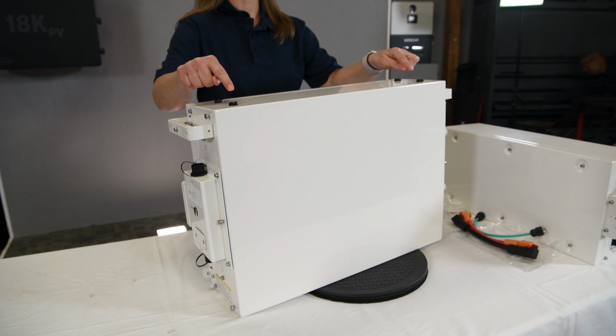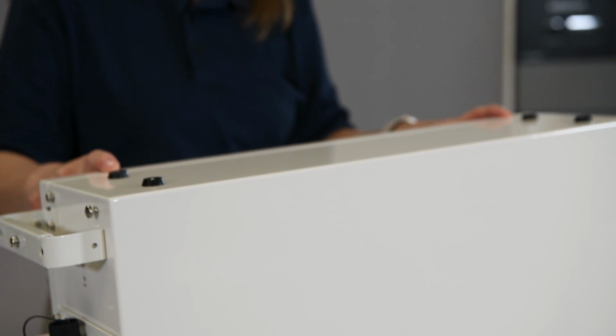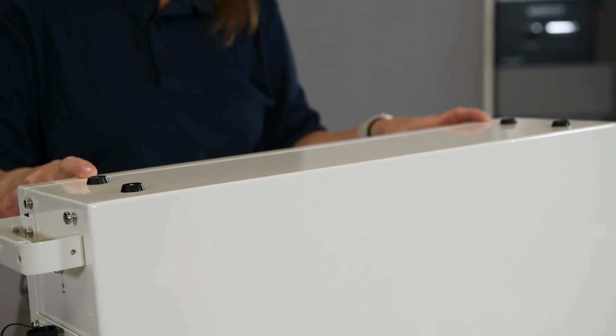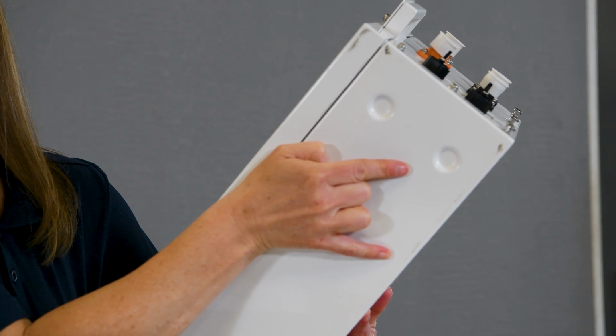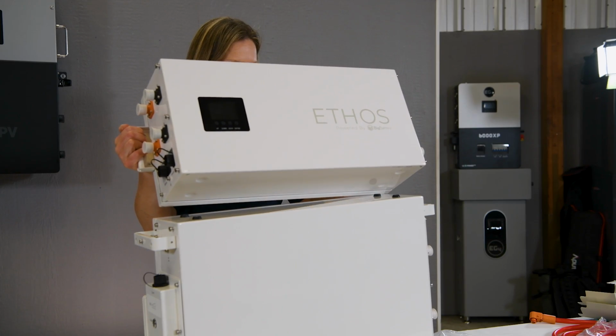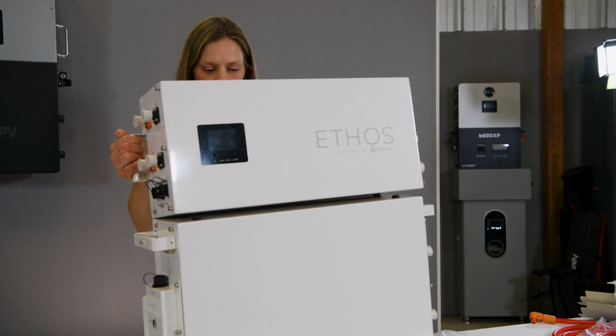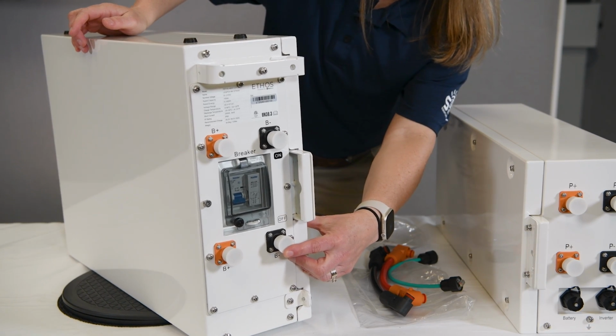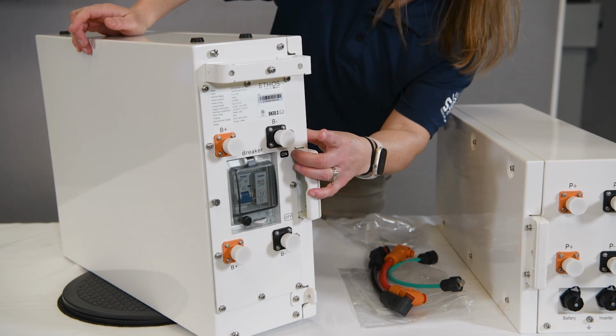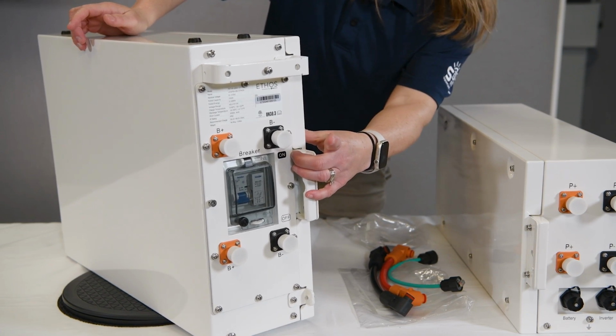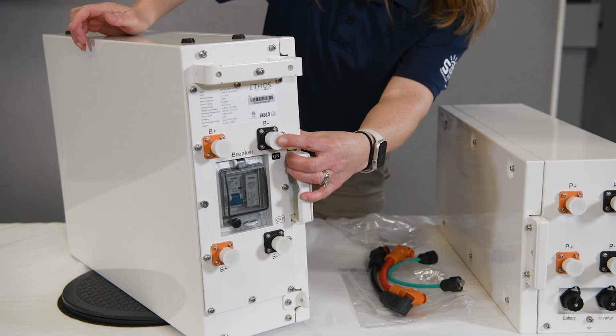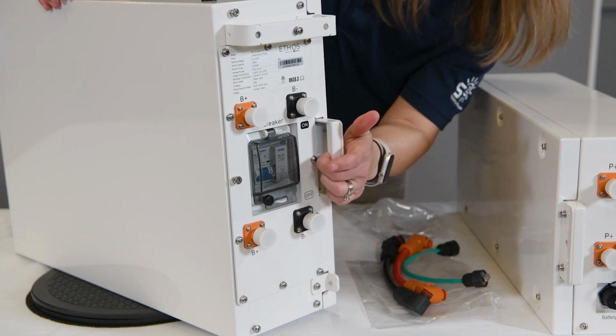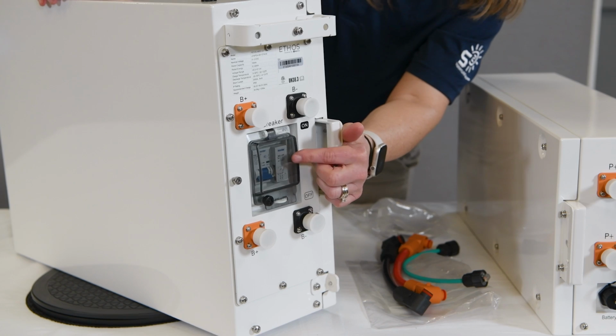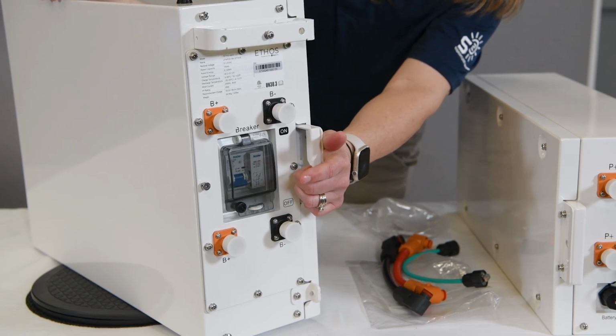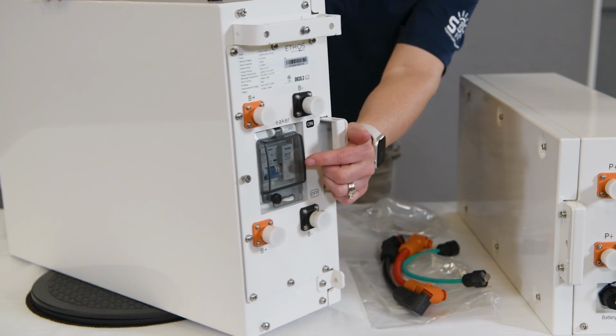The rubber points you'll see are designed for alignment, allowing additional modules to be stacked neatly on top. You can easily see how this works by looking at the bottom of the controller box. On the right side at the bottom, you'll find the positive and negative input terminal leads, while the top houses the positive and negative output terminal leads. Additionally, each unit is equipped with a built-in 125 amp DC breaker for added safety and protection.